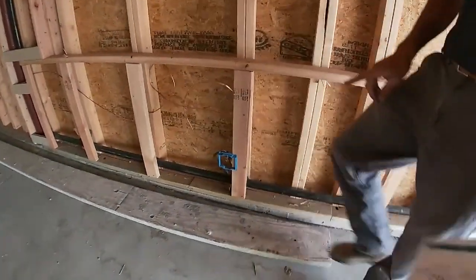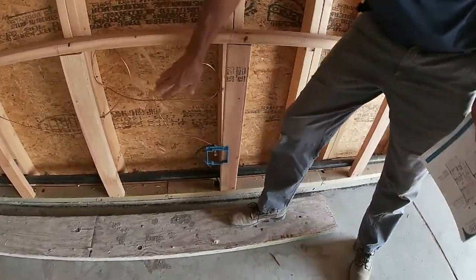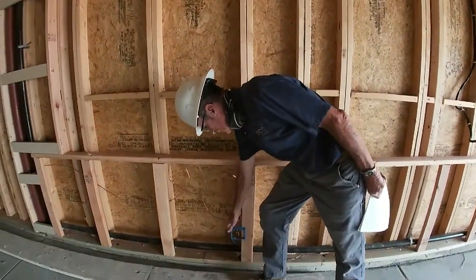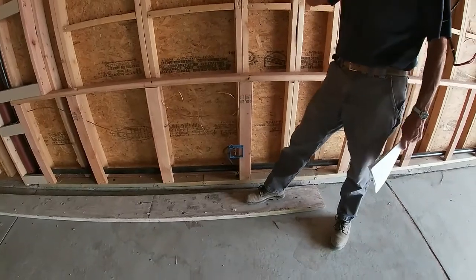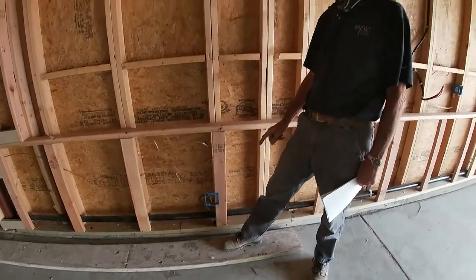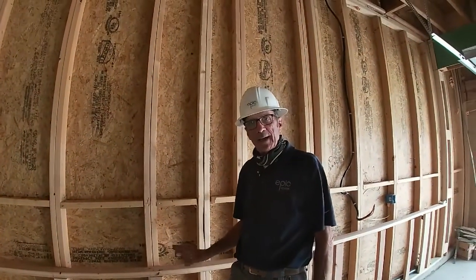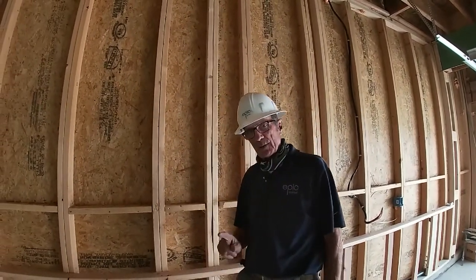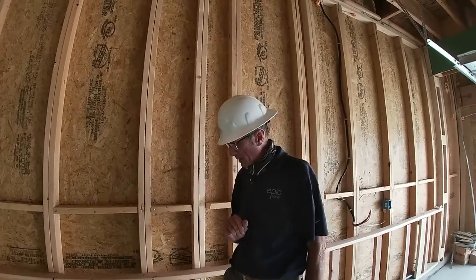This is a ground location, one of your electrical whole house grounding systems. We've got a rod installed. There's a piece of rebar there, which goes all the way down through the foundation into the ground, and that's called a concrete encased electrode, or a UFER ground, and that's our second means of ground. I'll talk about our first means of ground when we get to the basement.